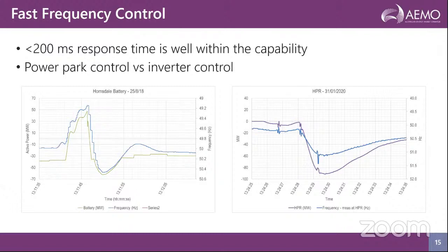And also it would depend on where the frequency is being measured. What our experience says is that some large-scale batteries measure frequency at the power park control level and then send a signal to the inverter. So the inverter would change its output to respond to the frequency change. While some measure the frequency at the inverter level itself. So those responses could be faster because that means there is no delay between the PPC and the inverter.